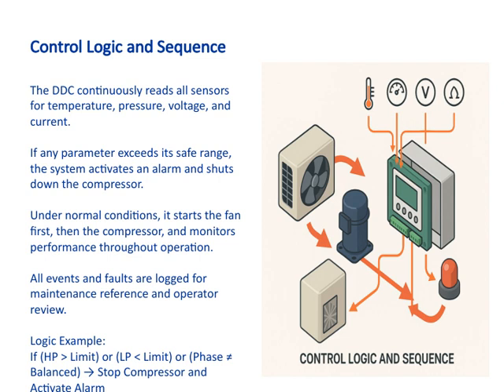To give you a clear example of the logic at work, if the high pressure exceeds its limit, or the low pressure drops below its limit, or if the phases aren't balanced, then the system will stop the compressor immediately and activate an alarm. This logical approach helps us prevent potential damage and maintain system safety. So overall, this control logic forms the core of our system's safety and operational reliability, making sure everything runs smoothly and safely.